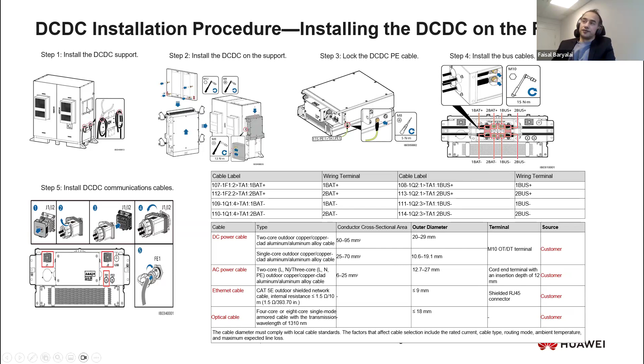When installing the PCS, we need a torque meter, applying 49 newton-meters. There are different torque values for different parts of the battery — the modules have a different torque. These are the small details that need to be taken into account. For instance, the copper bars also need to be adjusted to a certain torque level. If there are problems with this, it can affect the warranty — these are things we look into when we inspect the site, to check if it's done properly.